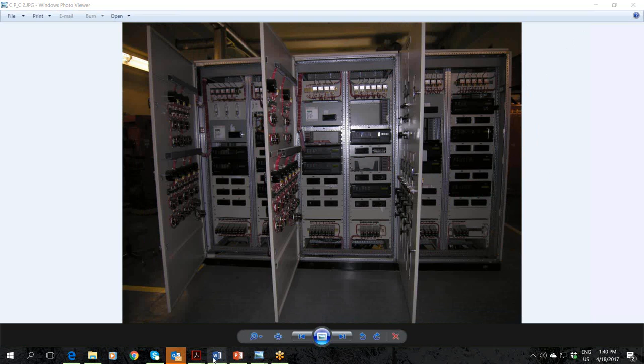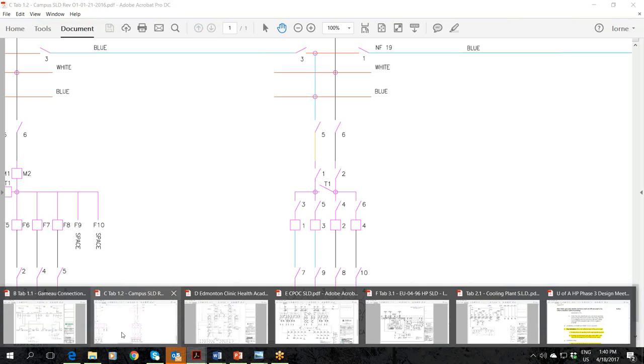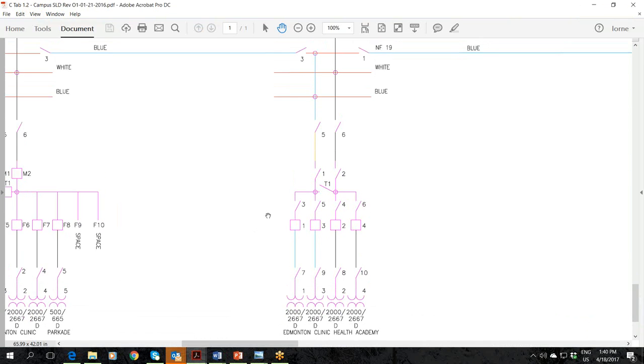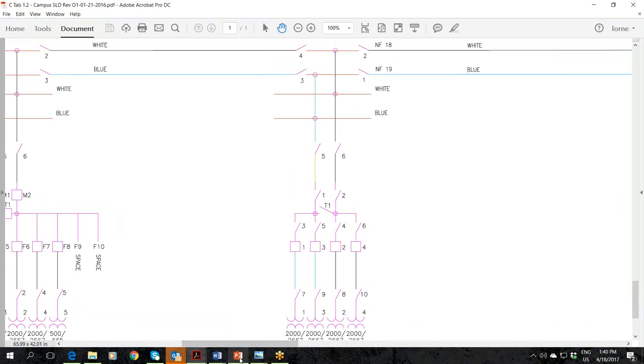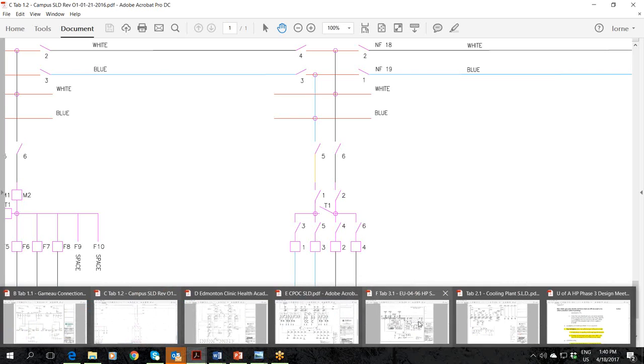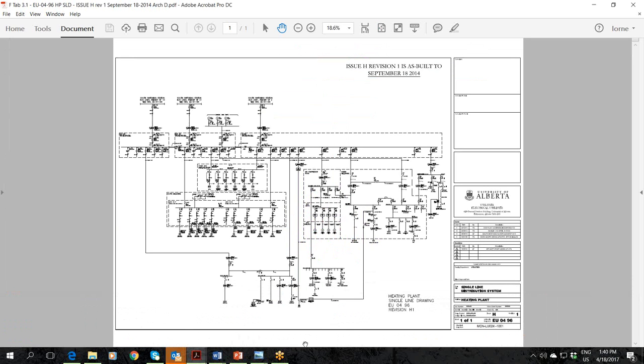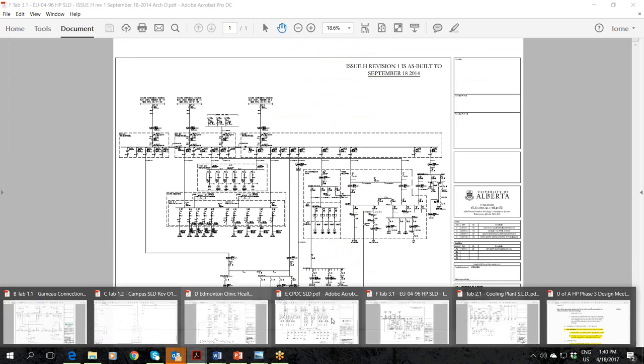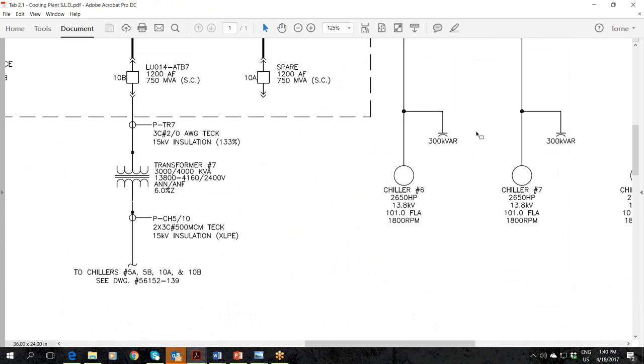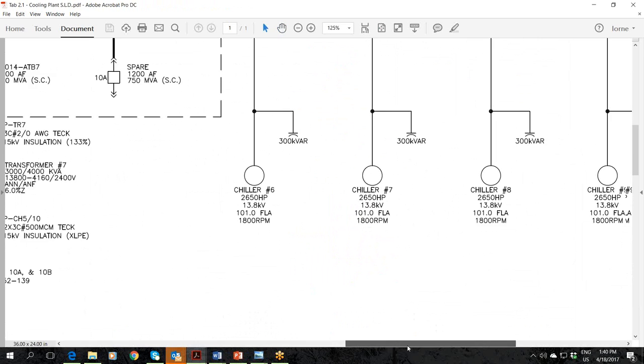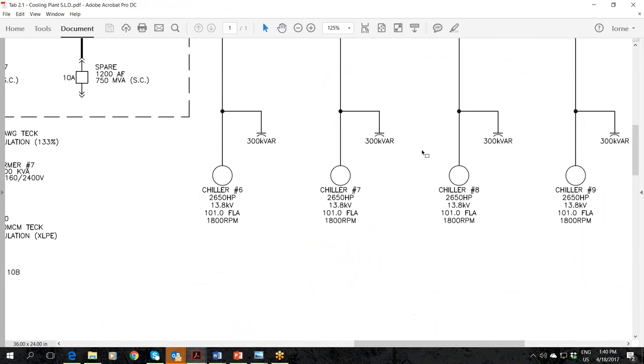I think there was a question that popped up on power factor correction. How are you doing that with your medium voltage chillers? We do have some capacitors on just the large motors. I believe the chillers, let me go back to that single line. Nope, close. Yeah, so you can see them here. We have them directly associated with the individual motors where it's required. Okay, 10-4.